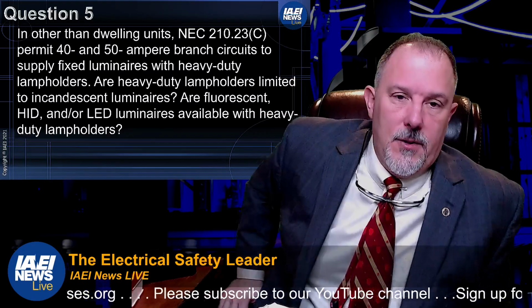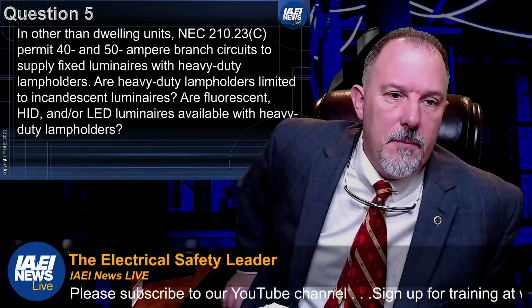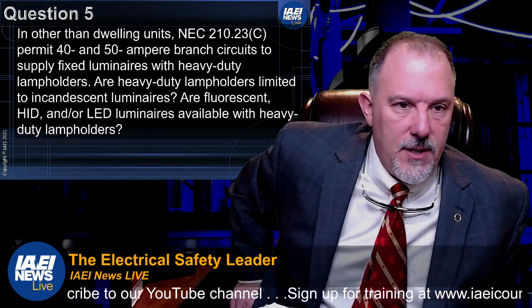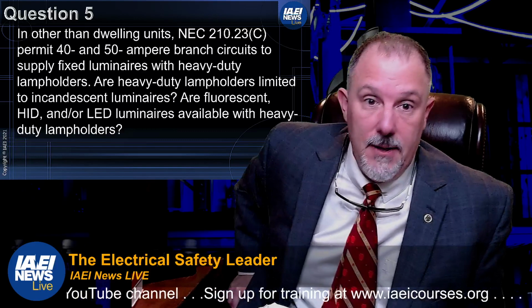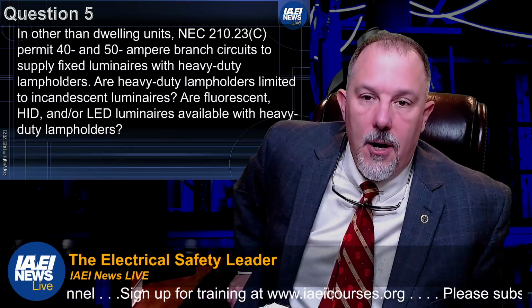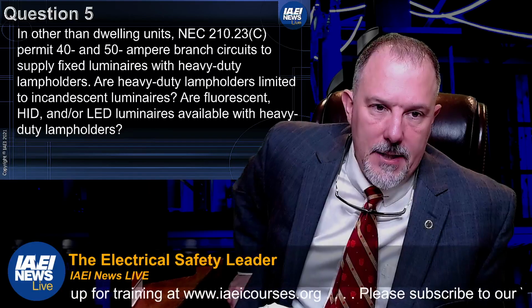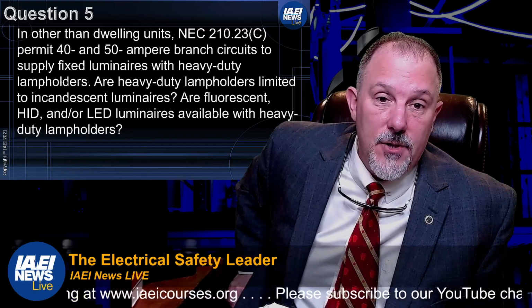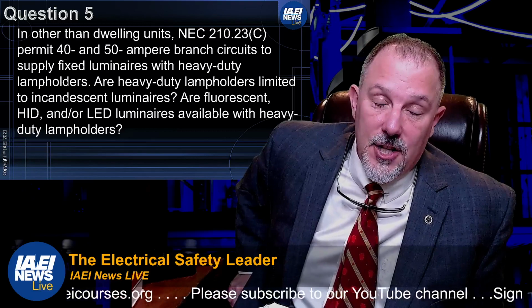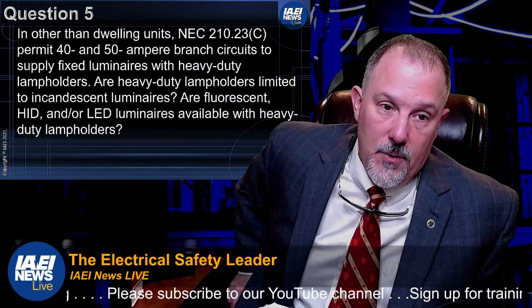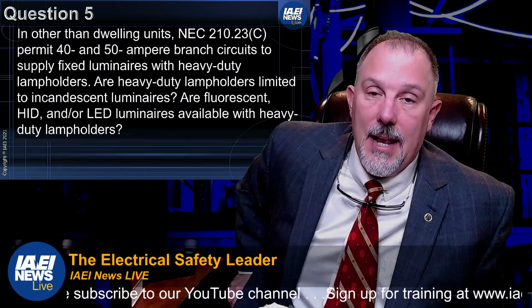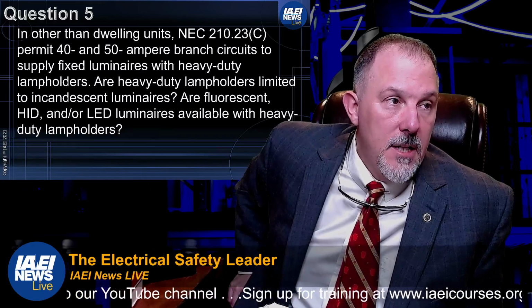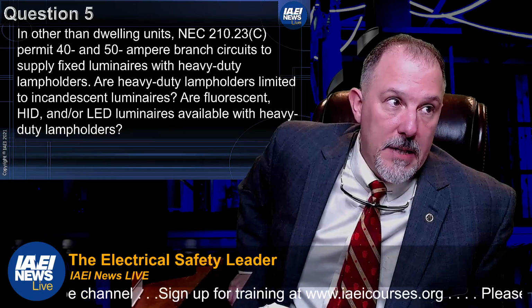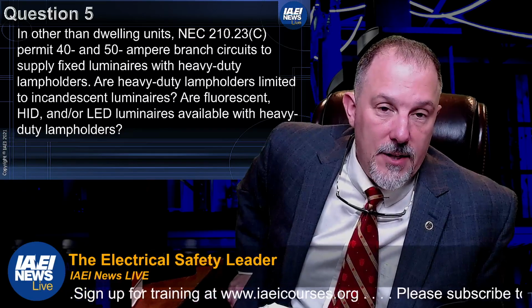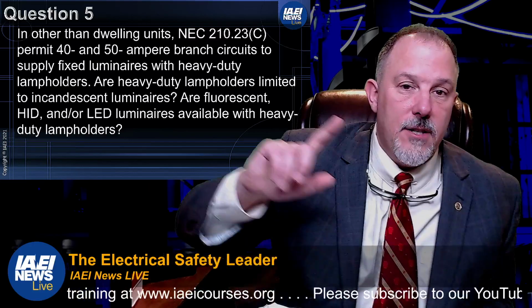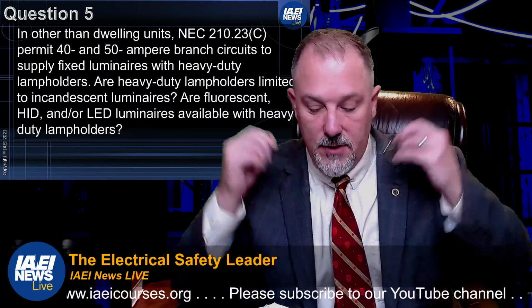In other than dwelling units, 210.23(C) permits 40 and 50 ampere branch circuits to supply fixed luminaires with heavy-duty lamp holders. Are heavy-duty lamp holders limited to incandescent luminaires? Are fluorescent, HID, and/or LED luminaires available with heavy-duty lamp holders? So, the first place I want to take you is 210.21. Now, 210.23 permits 40 and 50. So let's take a look at 210.23 first.